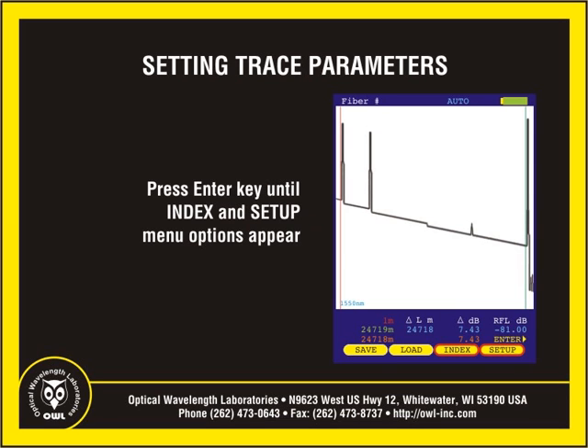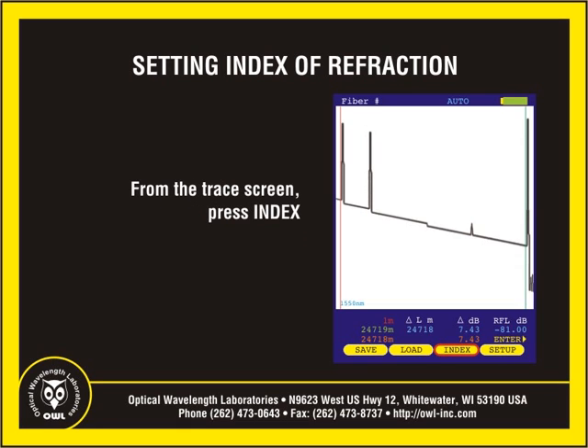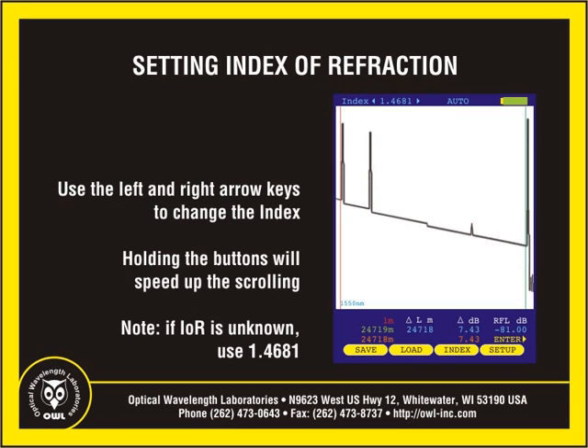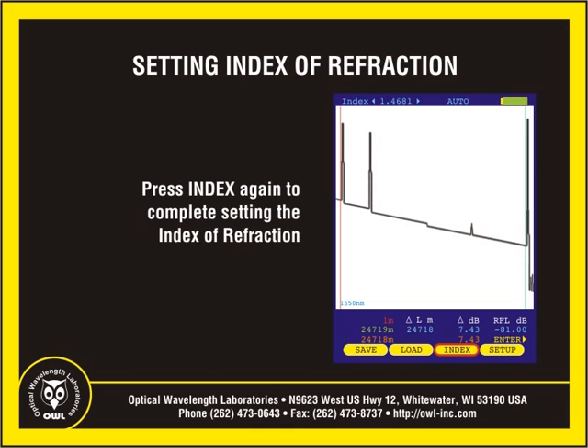From the trace screen, press the enter key until the function menu shows the index and setup menu options. To set the index of refraction, press the yellow function button below the index soft key. The index of refraction will appear at the top of the screen above the trace viewing area. Use the left and right arrow keys to change the value; holding the arrow buttons will speed up the number scrolling. Remember, if the actual index of refraction is unknown, use 1.4681. Press index again to set the index of refraction.